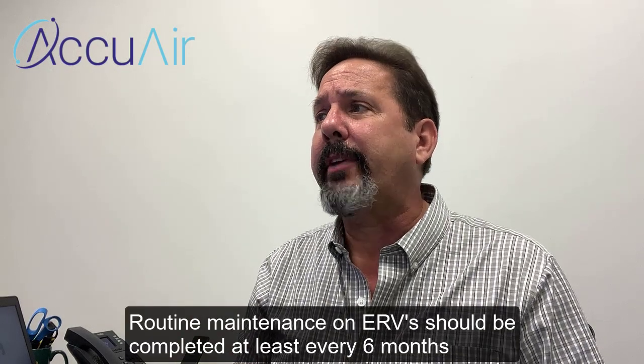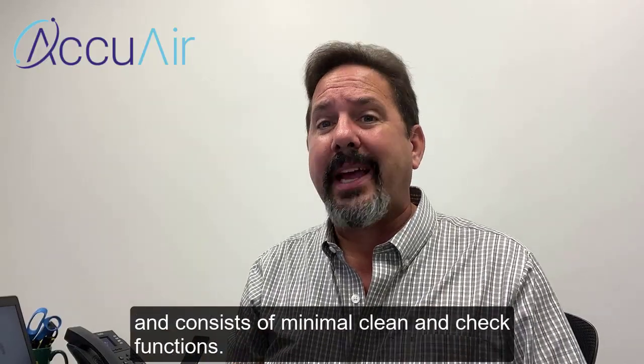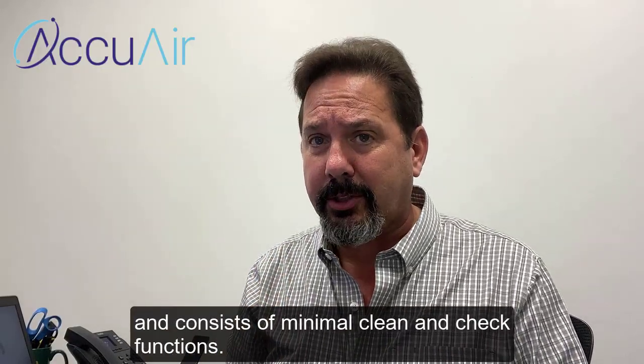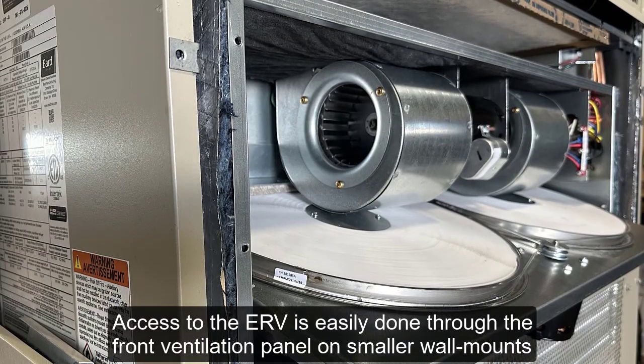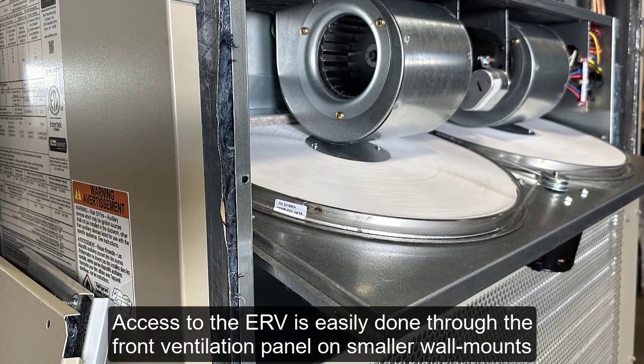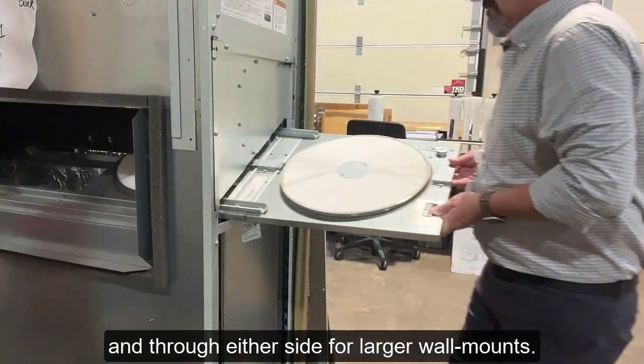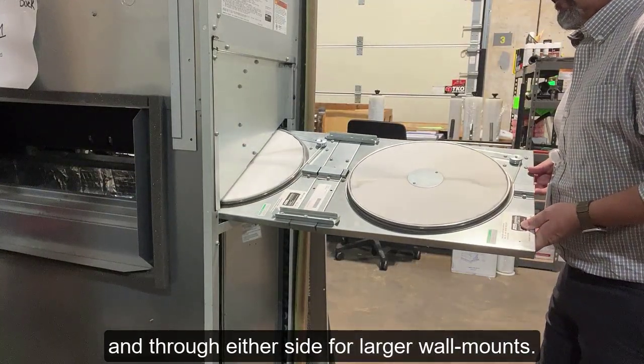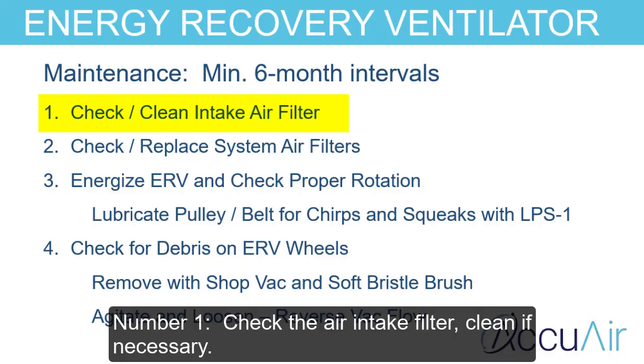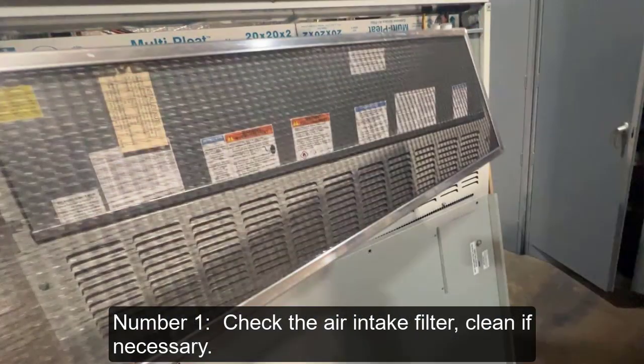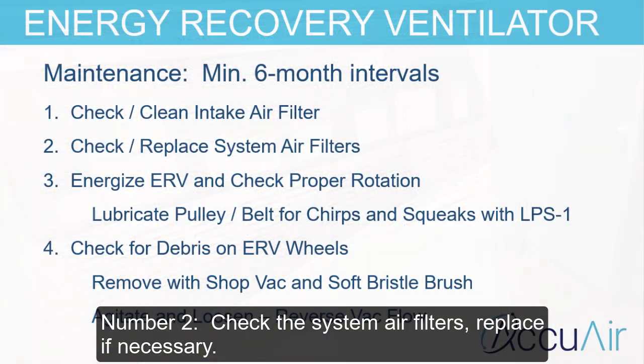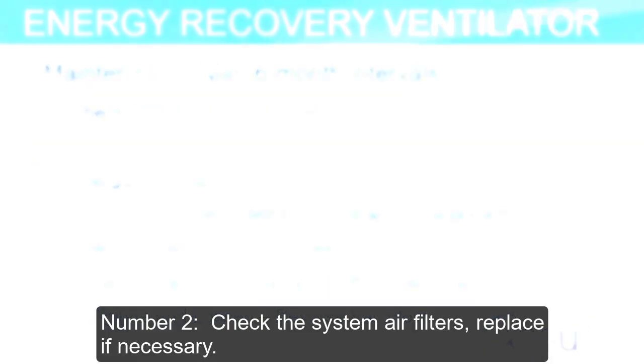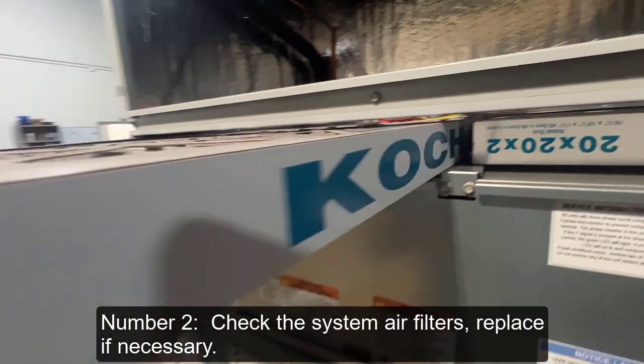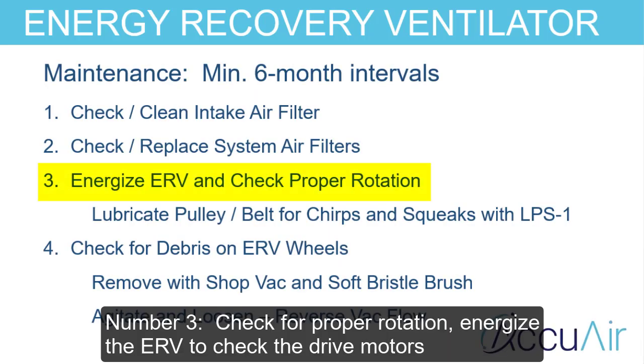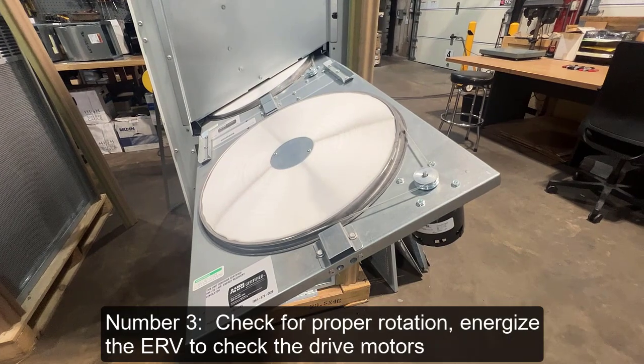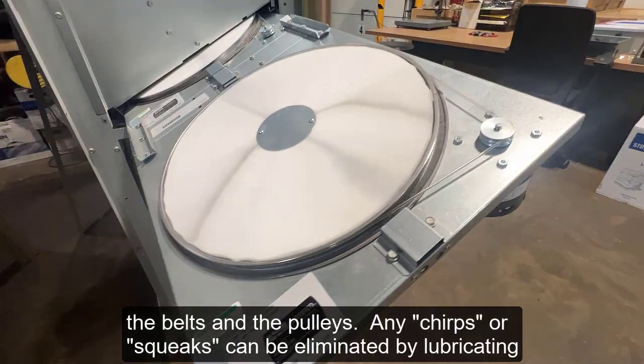Routine maintenance on ERVs should be completed at least every 6 months and consists of minimal clean and check functions. Access to the ERV is easily done through the front ventilation panel on smaller wall mounts, and through either side for larger wall mounts. Number 1, check the air intake filter. Clean if necessary. Number 2, check the system air filters. Replace if necessary. Number 3, check for proper rotation. Energize the ERV to check the drive motors, the belts, and the pulleys.